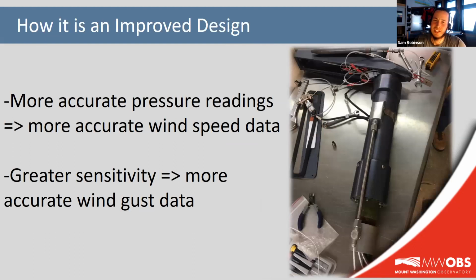So how is it an improved design, and how do these incorporated features actually benefit us? I may be repeating myself a little bit here from those earlier sections, but those were more along the lines of our initial goals for improvement, and this is how we were actually able to achieve those goals more specifically. So starting with the minimized length of the pressure lines, both the static and total pressure lines are about 6 inches in length, and that's quite a big difference compared to the 840 plus inches that are in Pitot 19 system. The pneumatic tubing and pressure transducers are fit right into the body of Pitot 22.